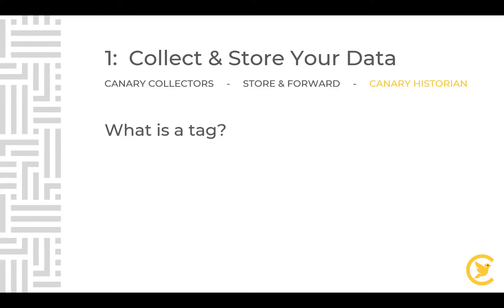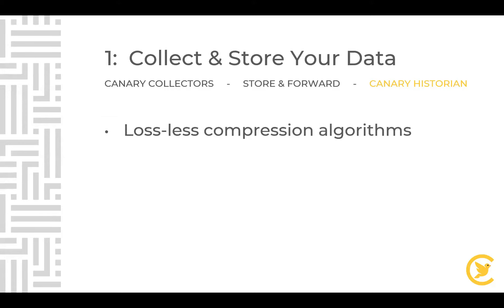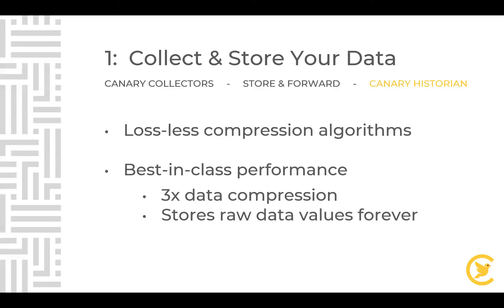A tag is a single stream of time-series data, also referred to as points, channels, or items. A tag consists of TVQ — timestamp, value, quality — and also metadata properties like engineering units, high-low set points, and GPS coordinates, which are all fully customizable. Once data is written to the Historian, Canary compresses it using a unique lossless compression algorithm with best-in-class performance — three times data compression. Because it's lossless, we are never interpolating data or cutting data values; the unique raw values are stored every time.